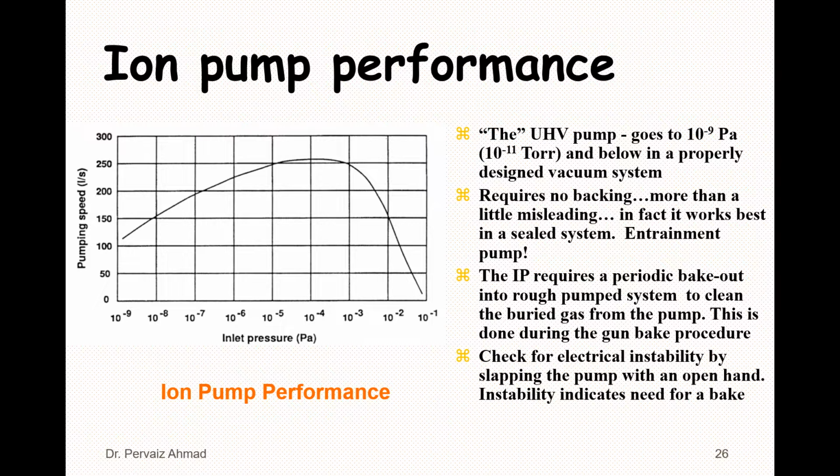Check for electrical instability by slapping the pump with an open hand. Instability indicates the need for a bake-out. So this is the ion pump performance.